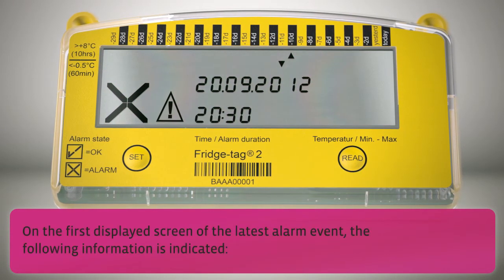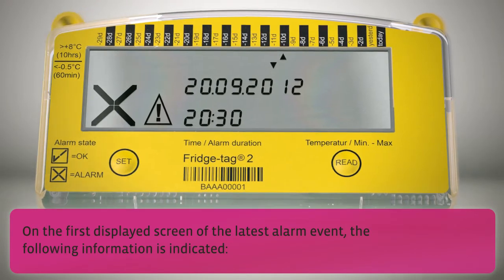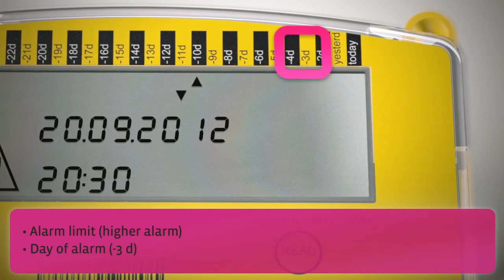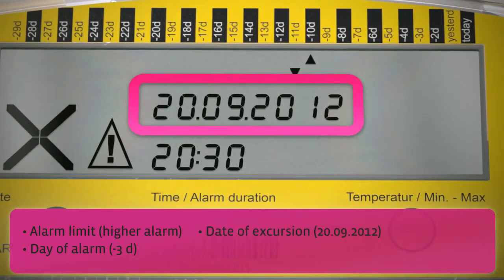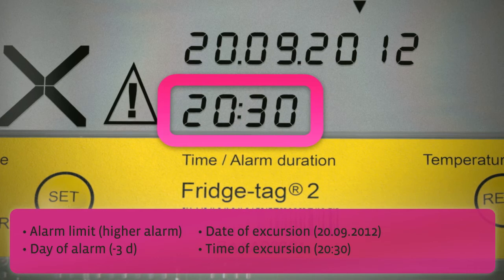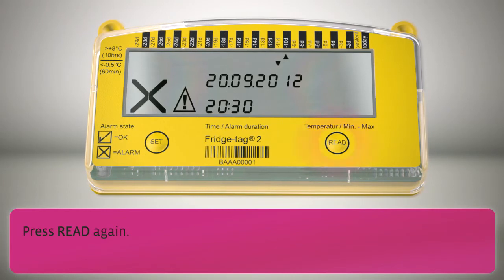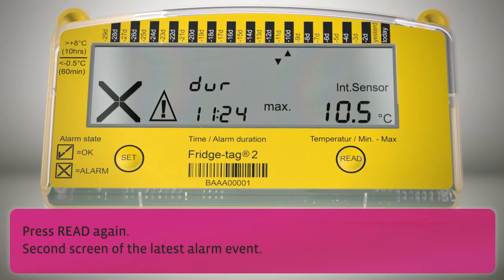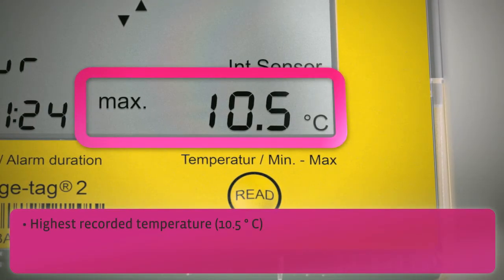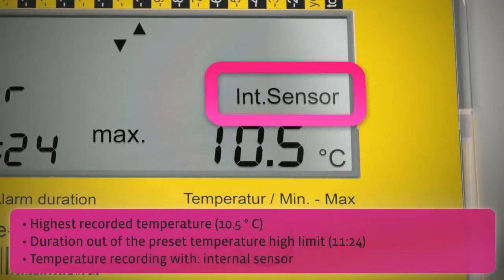On the first displayed screen of the latest alarm event, the following information is indicated: alarm limit, day of alarm, date of excursion, and time of excursion. Press read again for the second screen of the latest alarm event, showing: highest recorded temperature, time duration out of the preset temperature high limit, and kind of temperature recording.